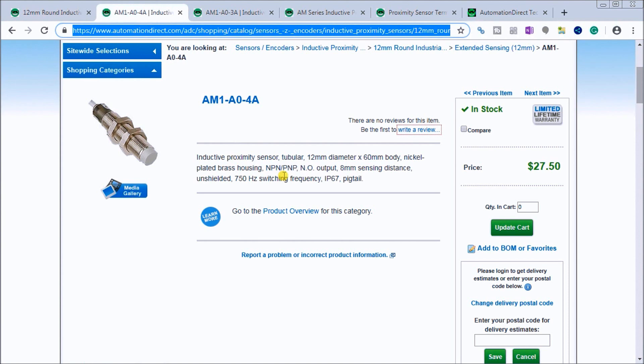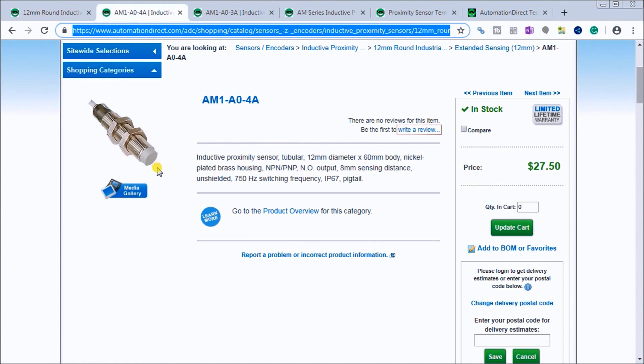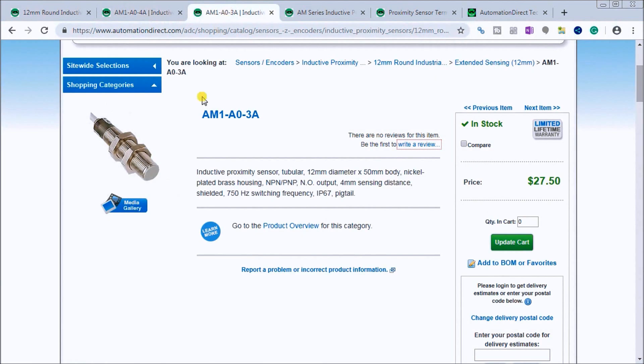It has an 8mm sensing distance. In our particular case, ours is not threaded to the end, so this is an unshielded sensor which gives us a little more range. We can look at the shielded one which actually comes to the very end so all the threads go right up to there and we can mount that flush.